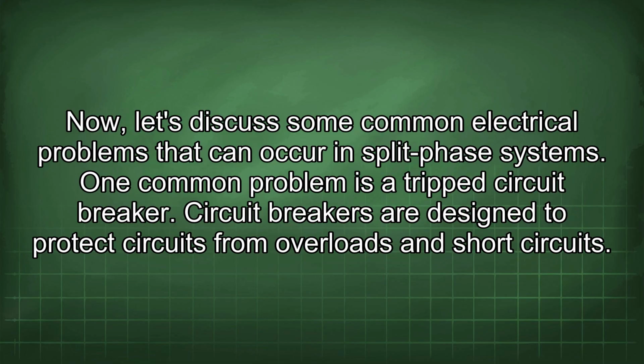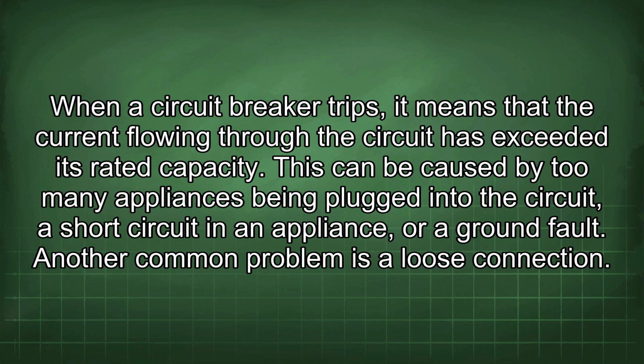Now, let's discuss some common electrical problems that can occur in split-phase systems. One common problem is a tripped circuit breaker. Circuit breakers are designed to protect circuits from overloads and short circuits. When a circuit breaker trips, it means that the current flowing through the circuit has exceeded its rated capacity. This can be caused by too many appliances being plugged into the circuit, a short circuit in an appliance, or a ground fault. Another common problem is a loose connection.